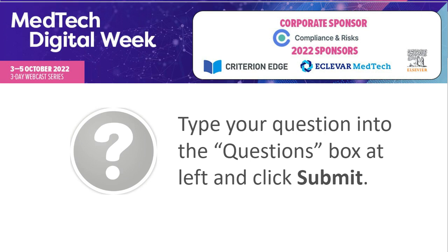First question, how would you integrate clinical evaluation into the design and development process? That's a great question. How do you integrate clinical evaluation and the considerations for your clinical evaluation needs into one of the very earliest stages, which is the design and development process? So we've got some ideas about that. For example, one thing that I didn't mention in this webinar is the importance of having identified your key safety and performance objectives that you will be using in your CER for the device under evaluation.